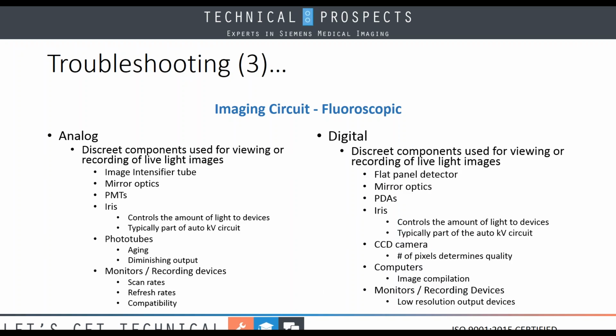In our digital world, you can see we have a whole bunch of different components. We've moved on from the image intensifier to a flat panel detector. We still may have mirror optics determining where that output is going to go. And now we use the photodiode array, a little bit more sensitive than the photomultiplier tube. We have irises now that control the amount of light to the various devices, or to our camera, such as the CCD camera. Now, CCD cameras come in different pixel sizes, and that's going to help, again, determine the quality of our X-ray that we're looking at. We take the signal received by the CCD camera, and we send it off to a computer for image compilation. Then we send that compiled image to our monitor or recording device, and this typically uses a low resolution. What I'm talking about here is a 14-bit versus a 12-bit signal.